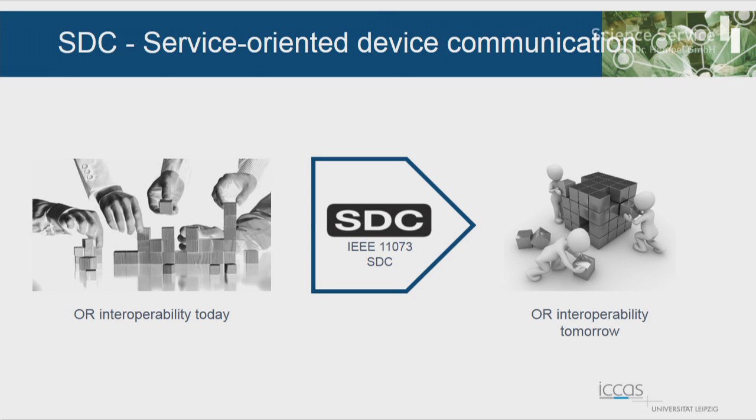It's a standard that was recently released. It's an IEEE standard called SDC, Service-Oriented Device Communication. This is the main interface description that enables this device interoperability, and the OR.NET User Association also cares about the standard and supports the vendors in integrating the standard into their devices, defining different scenarios for how we can develop the devices from currently not communicating devices to devices with open communication.